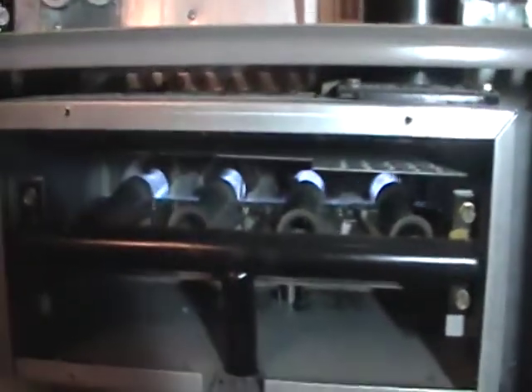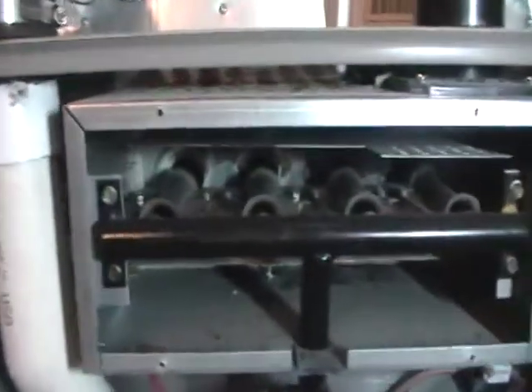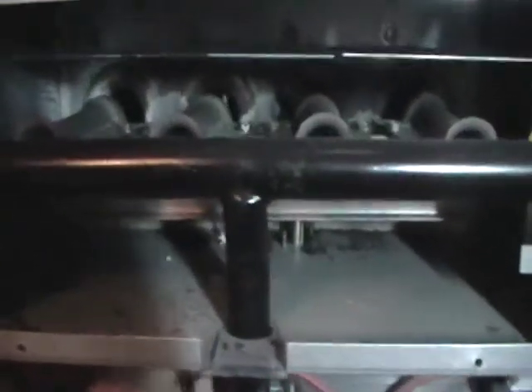Now, the flame rod is another piece of the furnace that we should generally clean annually. The flame rod being the part of the furnace that actually proves the flame. Flame rods basically take a signal from your control board, and through a process of flame rectification, the signal goes to ground, and that microamp signal ends up being the signal that proves the flame in the furnace. And it is a very small signal, so you want to make sure that this flame rod is generally as clean as can be. This one, I've taken the screw out. You can use a light rag or a very, very fine piece of sandcloth if it's heavily fouled. Now, after you've cleaned that, we're just going to reinstall it the same way.